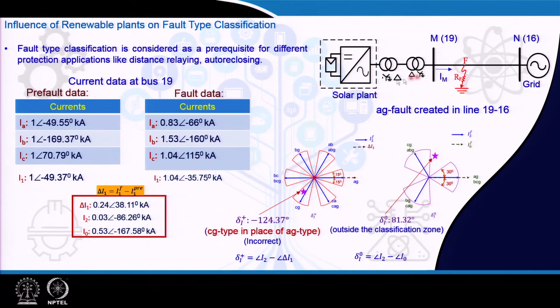This leads to the delta I positive sequence, the change in current from the fault current to the pre-fault current. This delta I 1 happens to be 0.24, the I 2 current happens to be 0.03, and the I 0 current happens to be 0.53. Note that this I 2 current is pretty small, insignificant here as already mentioned, and the zero sequence current finds a path.